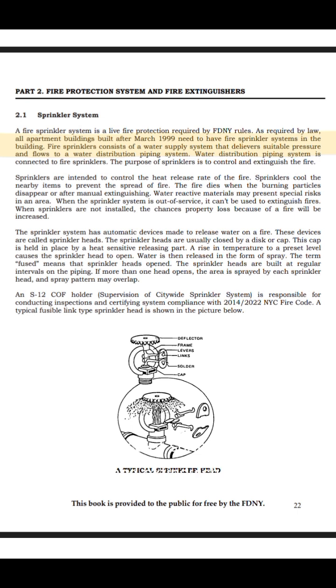The purpose of sprinklers is to control and extinguish the fire. Sprinklers are intended to control the heat release rate of the fire. Sprinklers cool the nearby items to prevent the spread of fire. The fire dies when the burning particles disappear or after manual extinguishing. Water-reactive materials may present special risks in an area when the sprinkler system is out of service. It can't be used to extinguish fires. When sprinklers are not installed, the chances of property loss because of a fire will be increased.